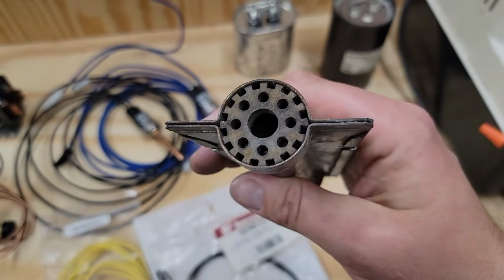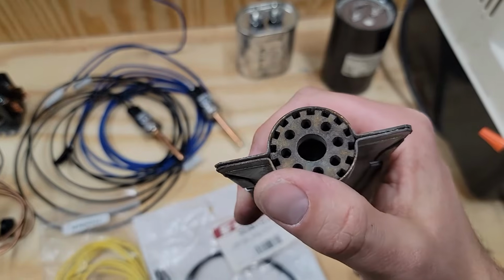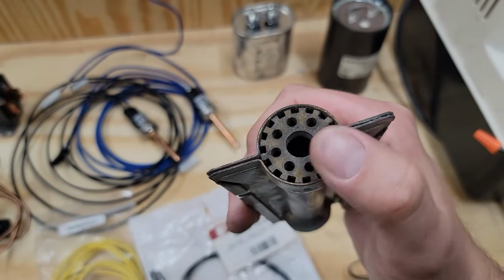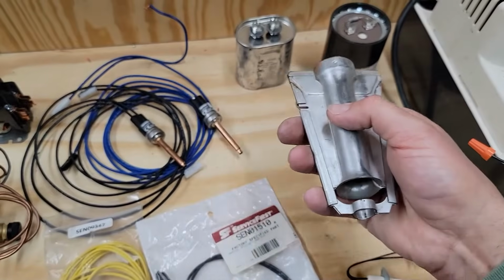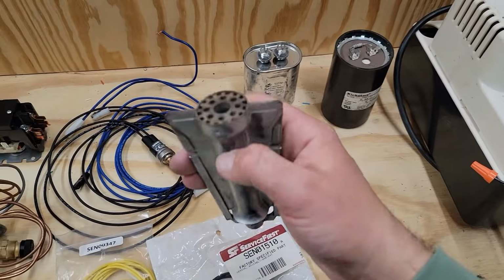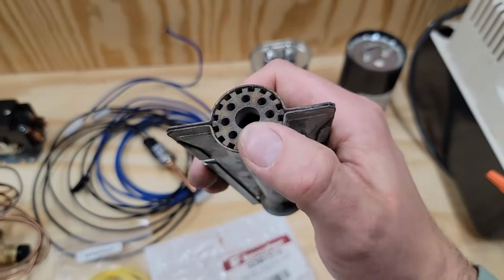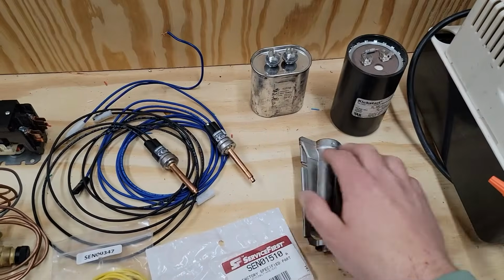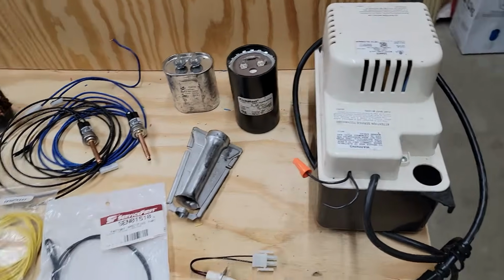And you'll want to clean this right here, because once the flame stops traveling across and you see 2 or 3 burners have flames, but then the other burner doesn't, you need to get some sandpaper. You need to get a steel brush to clean this off. That way the flame can travel, okay?